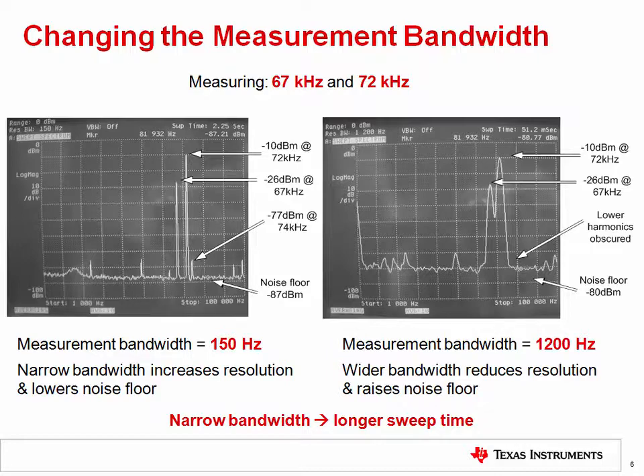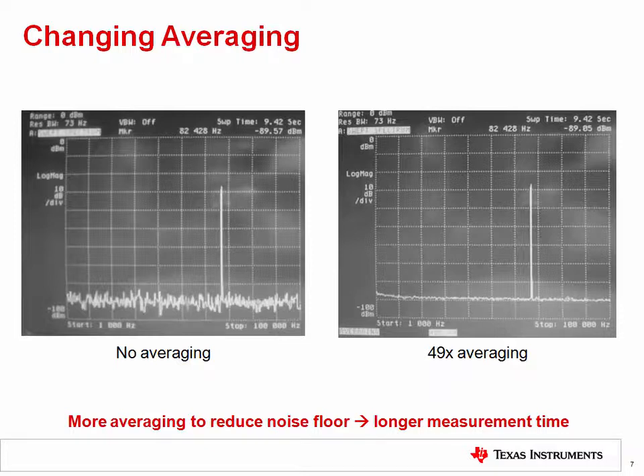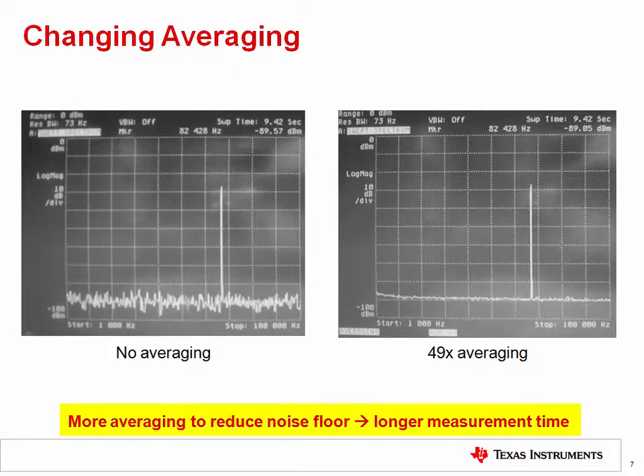Note that decreasing measurement bandwidth will increase the sweep time, essentially trading test time for improved accuracy. In some cases, for very high accuracy measurements, test times can take several hours, so it is not always practical to use an extremely narrow measurement bandwidth. Another way to improve measurement accuracy is to use averaging, which combines the results of multiple noise sweeps. In order to achieve accurate results, the device conditions need to remain constant. Averaging works very well for measuring spectral density, though it shares the same tradeoff — increasing averages for better accuracy will increase measurement time.